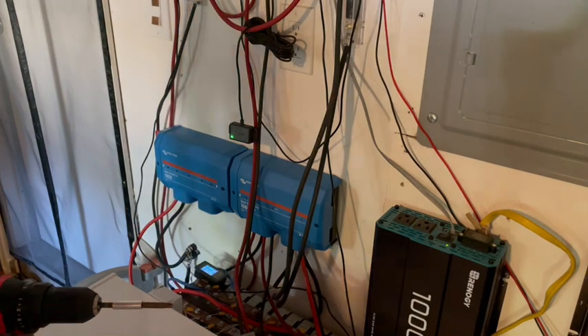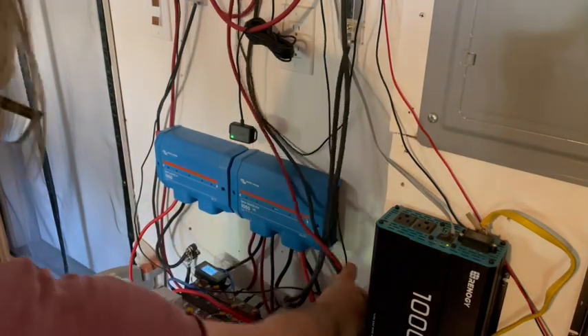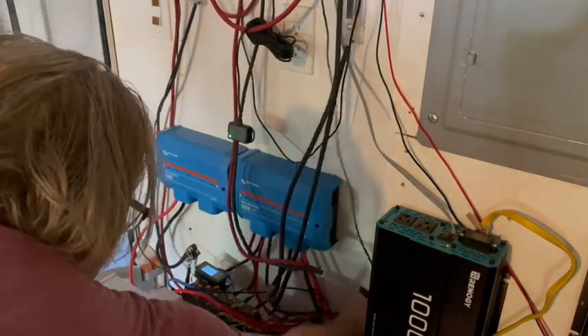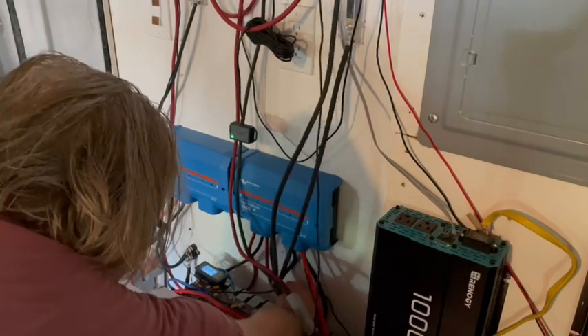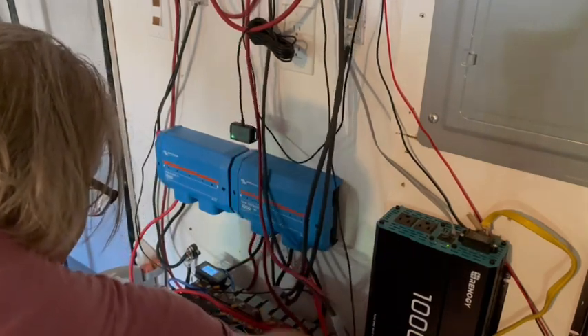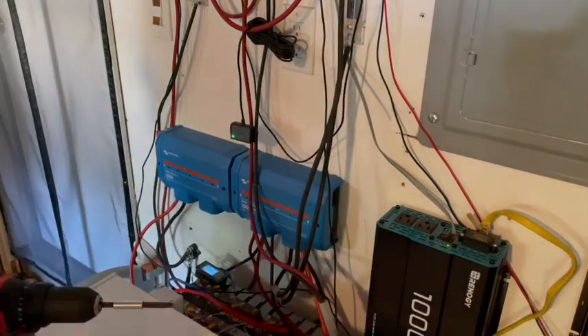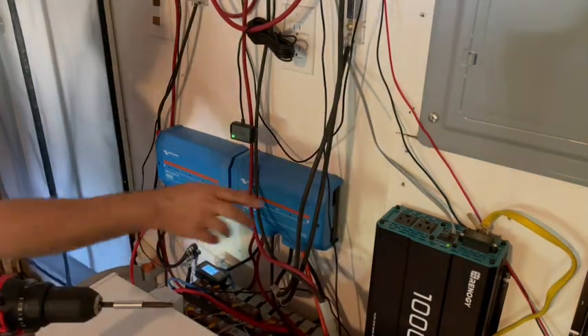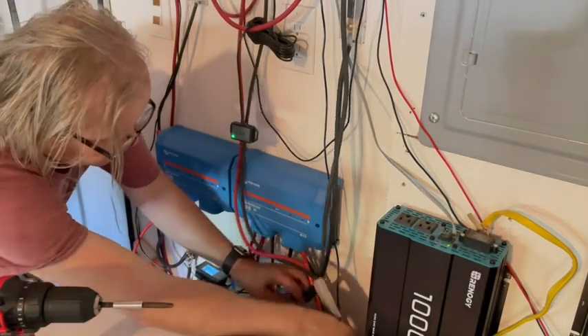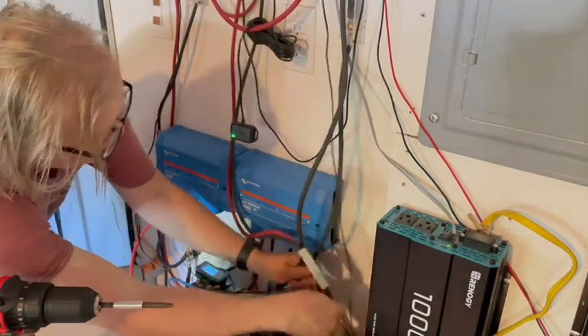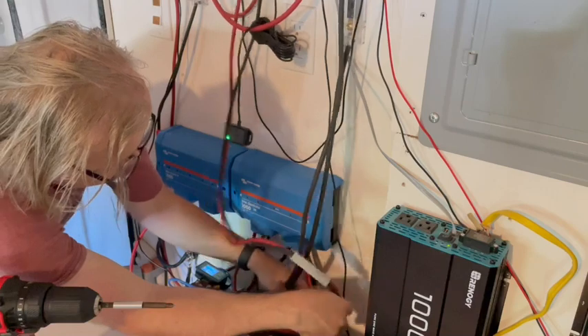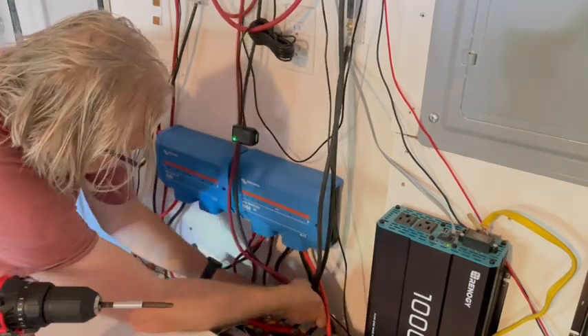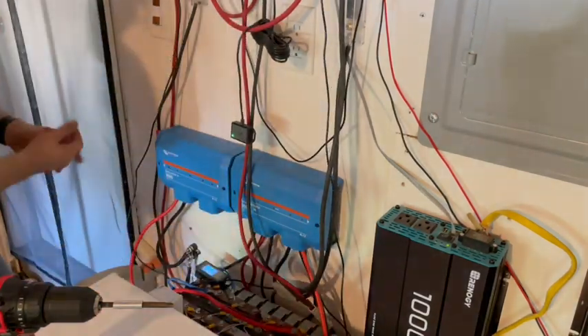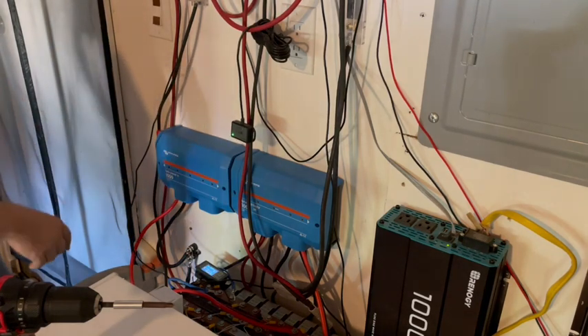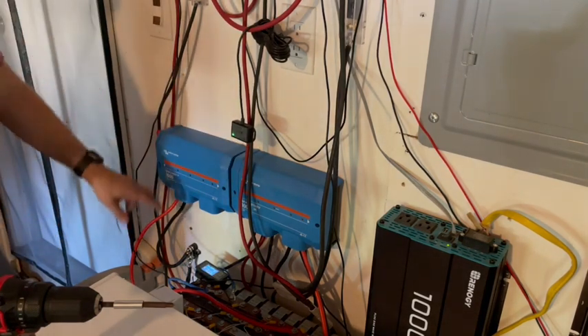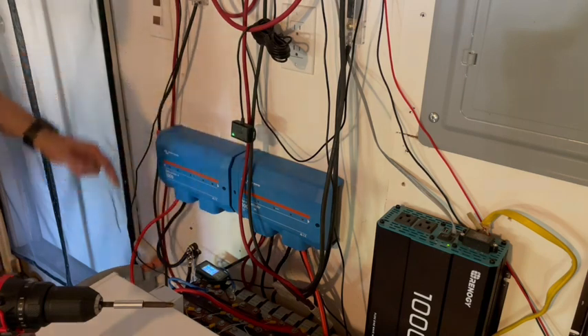There, that looks much better than before, a little safer with less exposed wiring. And these are connectorized here with 50 amp Anderson connectors. Each individual channel is less than 50 amps, so these connectors can handle the individual channels. They get combined in this Lynx system, so technically there could be 150 amps flowing through those 50 amp connectors.